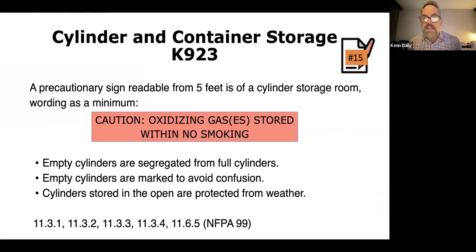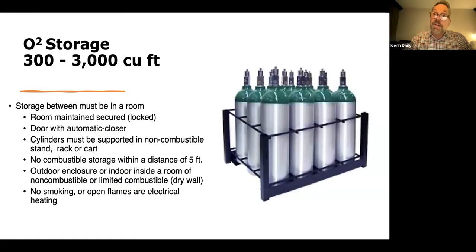That must be locked. The cylinders must be segregated, so the full and empties must be separated. Some method has to be done, and then it has to be protected. Has to be locked and protected. It must have an automatic closer on the door, etc. If you have between 300 and 3,000 cubic feet, the door has to be locked. Has to have an automatic closer on the door.